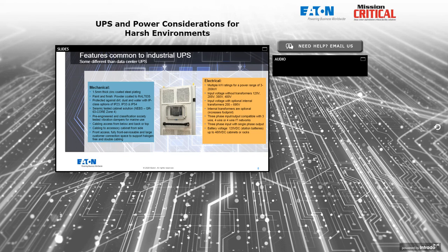Seismic tested cabinet solutions, NEBS, or Zone 4 or OSHPD, any and all of those are commonly requested and specified for industrial UPS. Pre-engineered vibration dampers for marine use. So what this means is, instead of the UPS sitting on casters or on leveling feet, they're actually rubberized or flexible vibration dampers, and the UPS would be bolted to the floor of the building or the deck of the ship and would be supported not only at the bottom, but often at the top of the cabinet as well, in such a way that it can absorb shock and vibrations much more severe than you would find in a stationary environment.